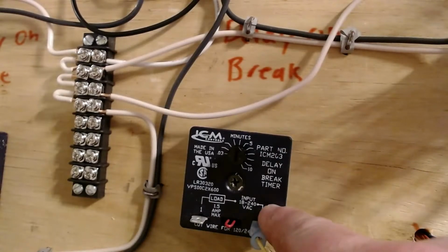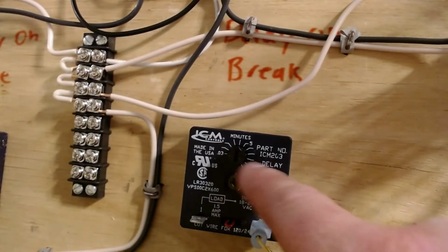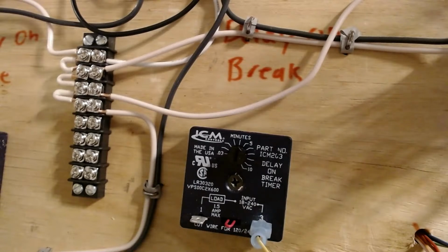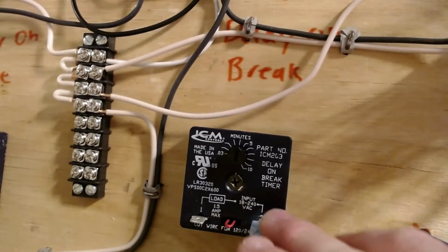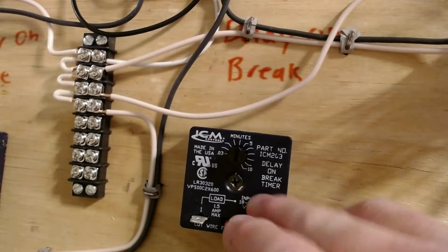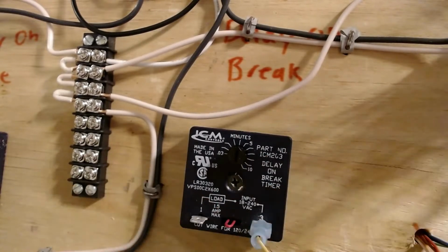So when power is calling in, once it breaks, it will start the timer. With the delay on make, it'll start the timer as soon as power is energized to it. So delay on break, timer starts once power is no longer being called. Delay on make, timer starts when power is being applied. So as soon as this loses a call, it starts the timer internally. As soon as the make gets a call, it starts a timer internally.